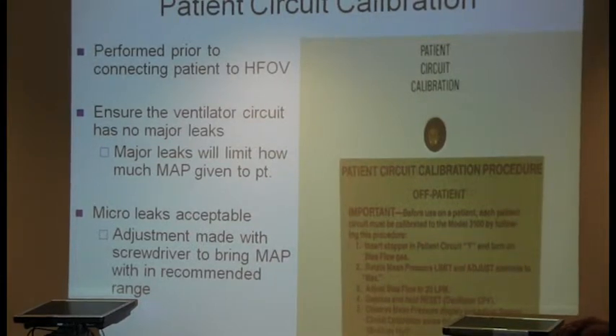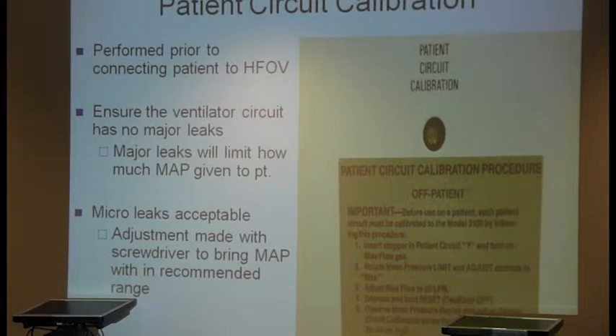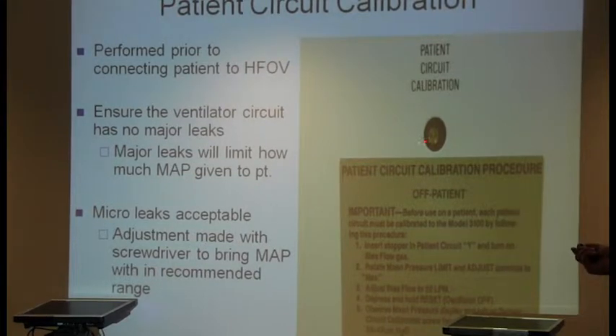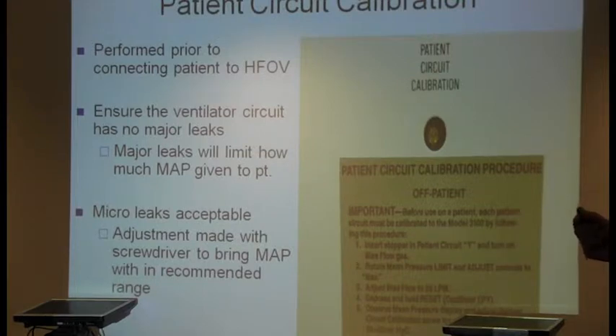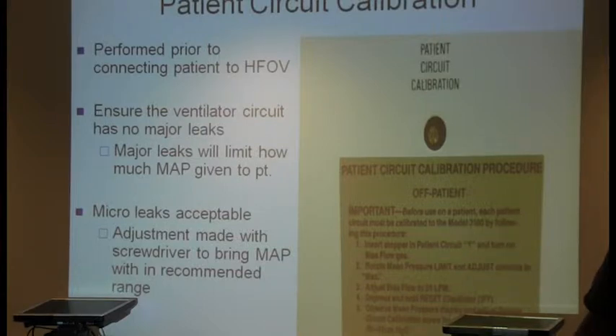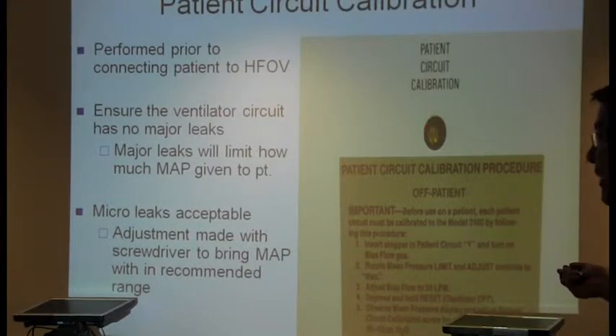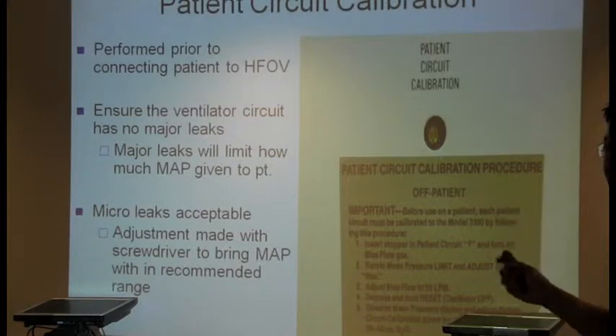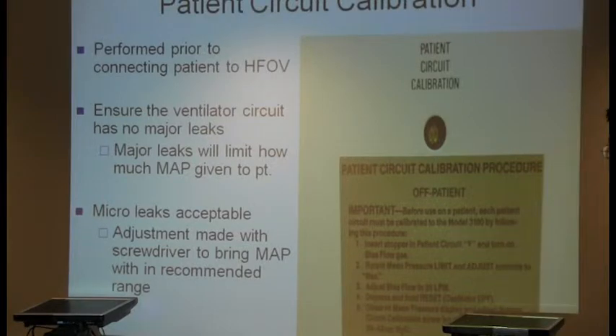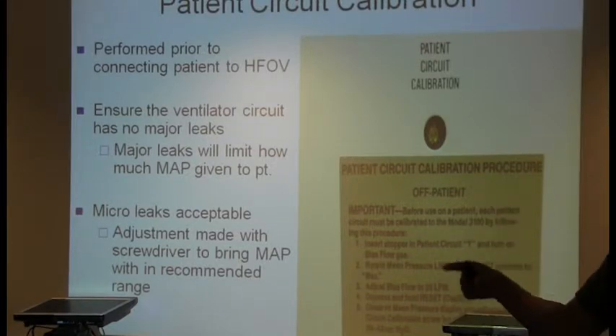But if my number says 34, 35, that's a huge leak. So when you do this, you're going to be cranking this puppy all the way clockwise until it can't go anymore, and once you can't go anymore, you can potentially strip it and ruin the ventilator for any future usage. So please don't use this for major leaks. When that number is a 35, that means your circuit has a huge leak, so you need to troubleshoot it.